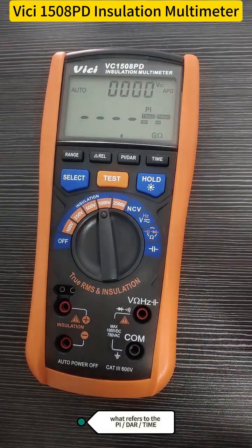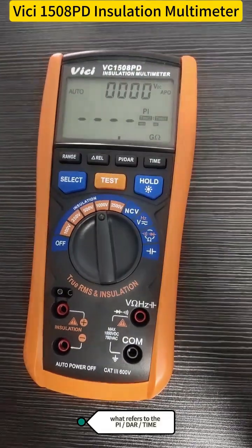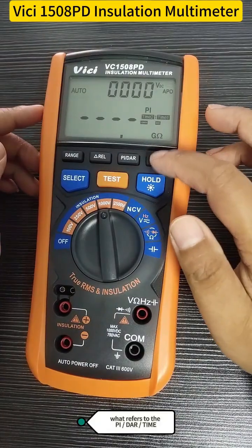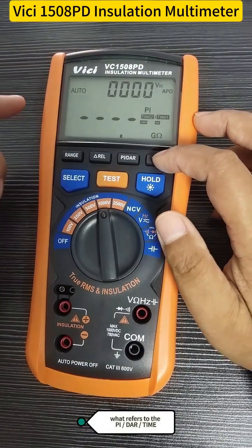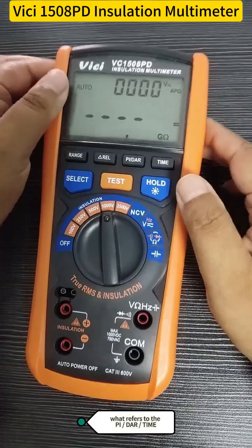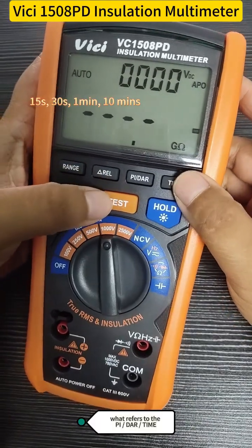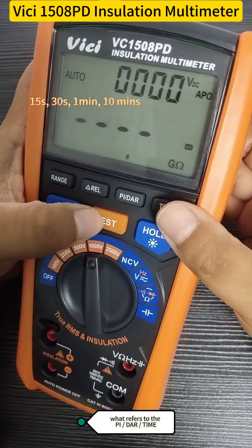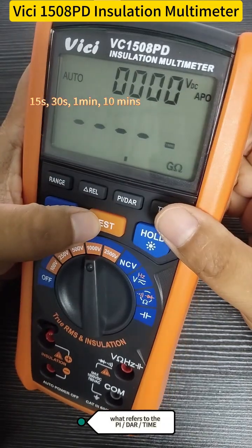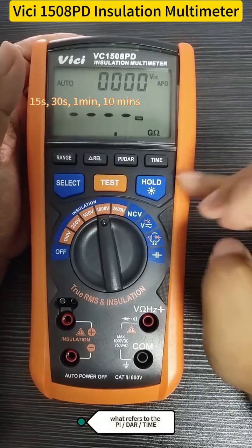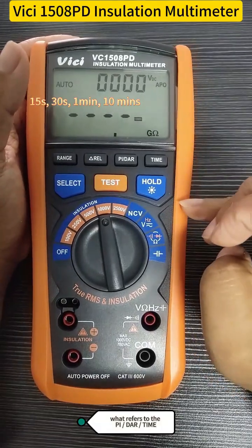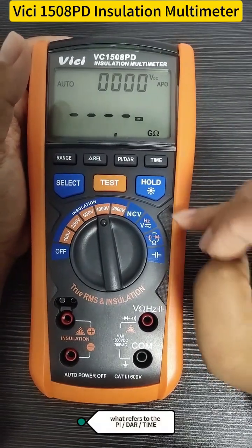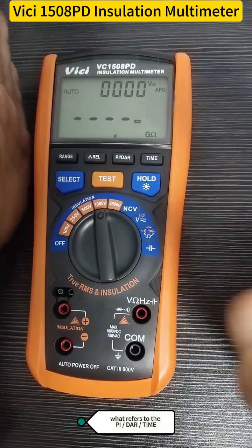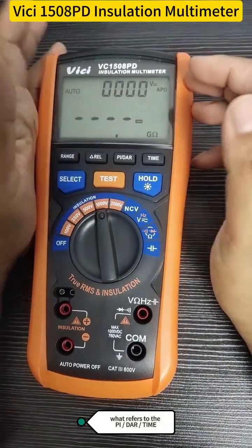Another useful function of this tester is the time button to set test durations. It's for 15 seconds, 30 seconds, 1 minute, and 10 minutes. The meter handles the timing automatically, super handy for on-site work. This is the insulation functions of this tester.